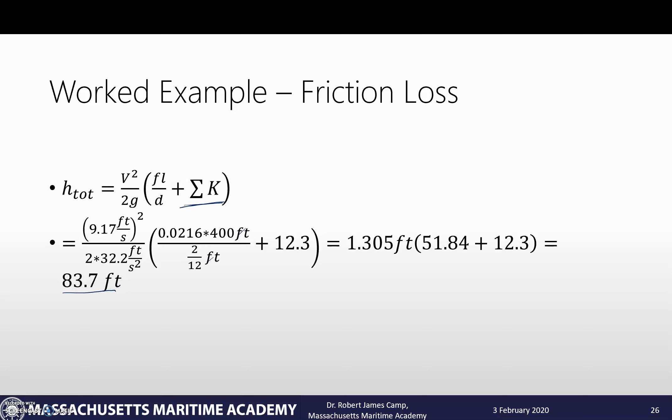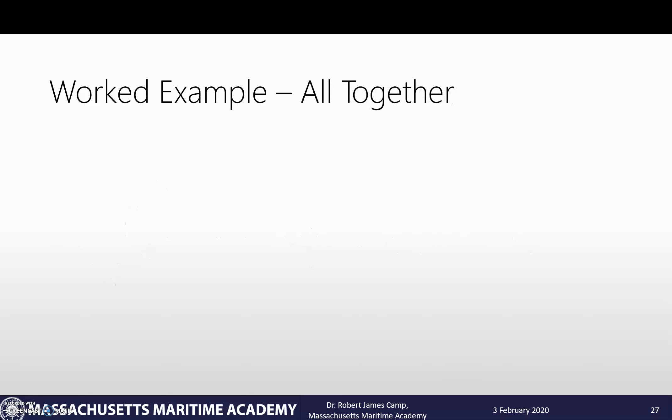Now if we go back to our initial problem and plug that in, we have 120 feet minus 20 feet plus 83.7 feet. That will give us the pump has to put in 183.7 feet of head to overcome the gravity and the elevation in our system.